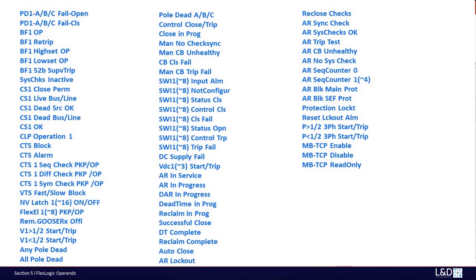On the second page of operands, you can see counters, alarm, group change, pole discrepancy (PD), breaker failure (BF), synchronous check, CLP, cold load pickup. These specific operands will be covered when we get to protection element modules 104 and 105. There's also voltage elements — under voltage, over voltage — the monitoring, and switches. And lastly is auto reclose. Knowing this sequence of over 1500 operands is important for quickly identifying where an operand is in the list.